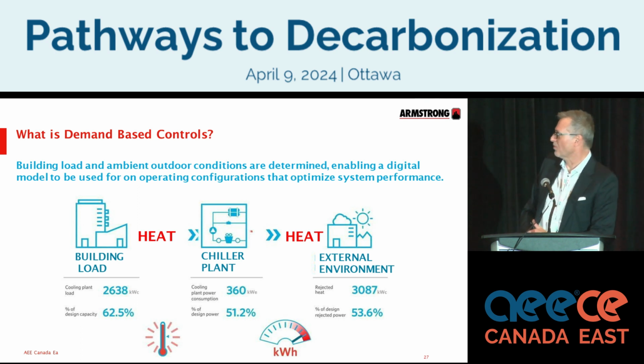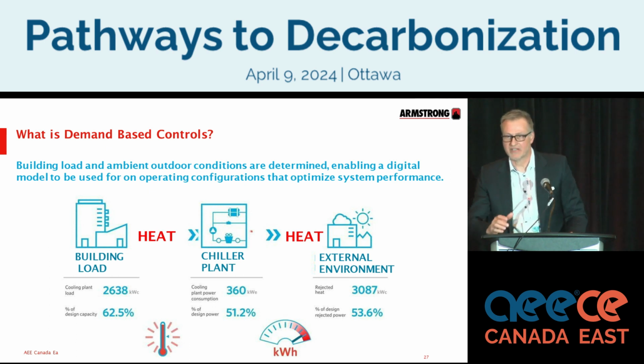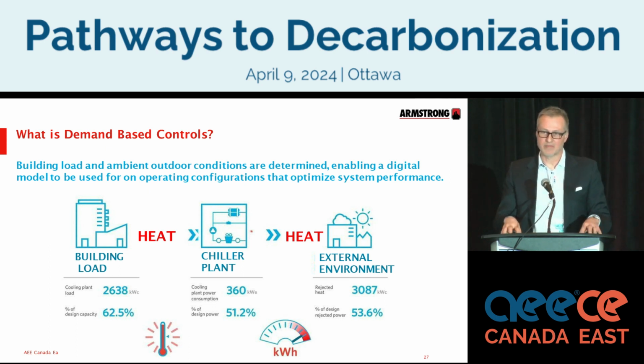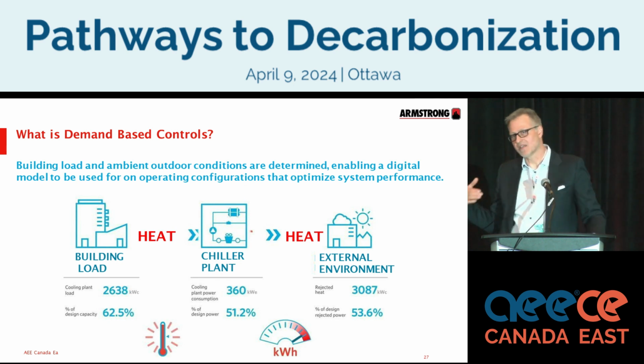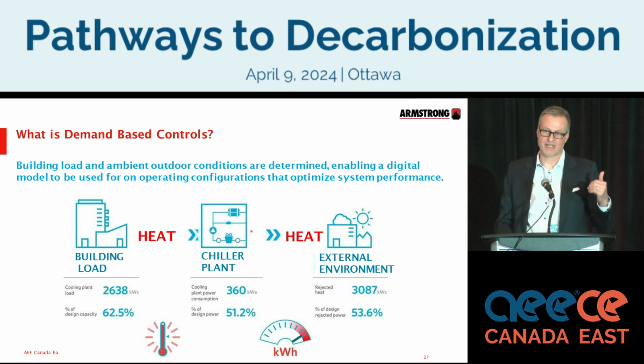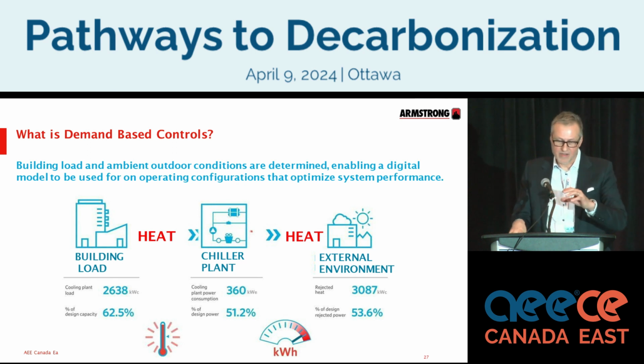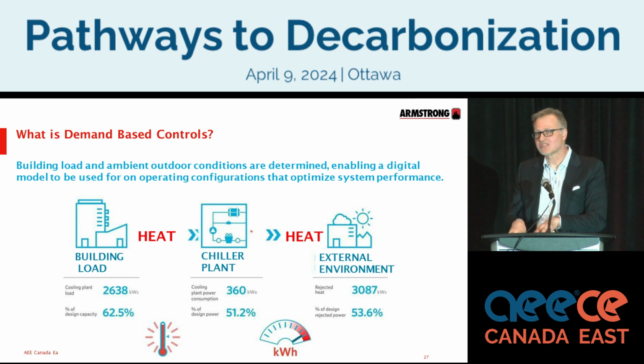So how does this work? Well, the building load and the ambient outdoor conditions are determined, enabling a digital model to be used for operating configurations that optimize the system performance. So basically, now the system becomes an equation, and you need to know what is the load inside the building. How many BTUs are we trying to move from inside the building to outside or to somewhere else? And then, what are the ambient outdoor conditions? So what's the temperature outside? Because the key here is understanding that the way a cooling tower is designed is that it has an ambient approach temperature to the atmosphere. And that's usually either 5 degrees or 7.5 degrees.